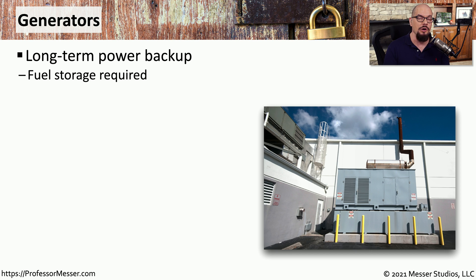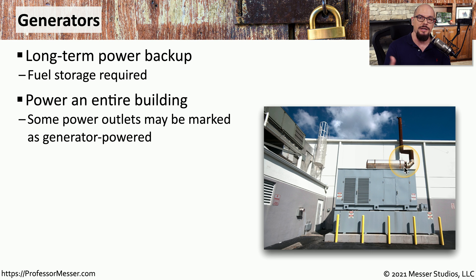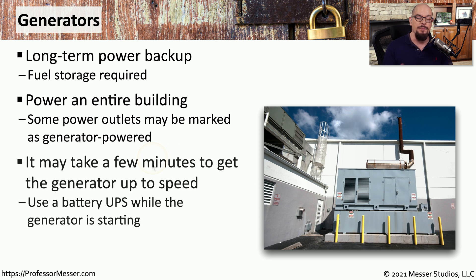If you need power to be maintained over a longer time frame, you might want to move up to a generator. A generator is a long-term power backup that can keep the power running for days or even weeks at a time, as long as you have fuel available. These generators can often power an entire building, or at least a number of outlets inside it. Often the outlets are marked to show they will provide power during an outage. Once the power goes out, there's usually a 10 or 15 second waiting period to see if the power turns back on, and if it does not, the generator turns on and begins providing power to the building. During that 10 or 15 seconds, you will need some type of internal power to keep your systems running, which is why you might combine both the UPS and the generator to make sure all of your computing systems stay active and available.